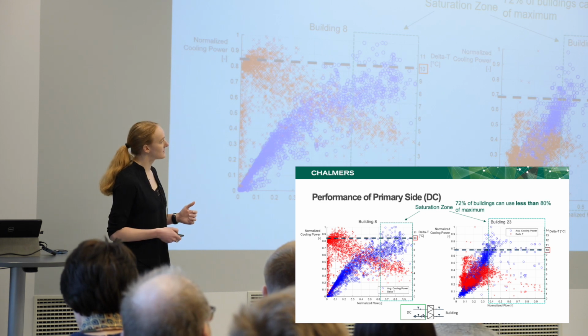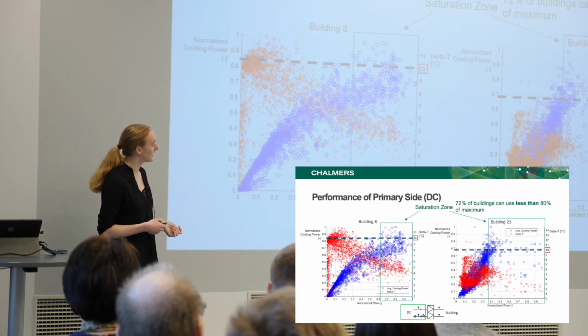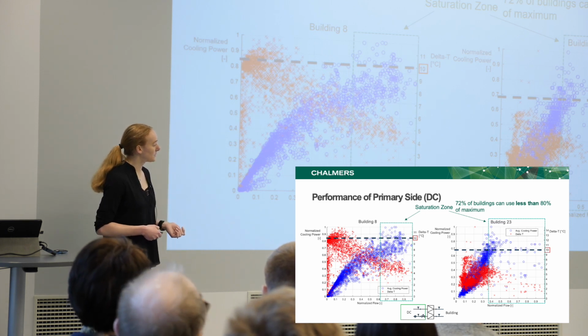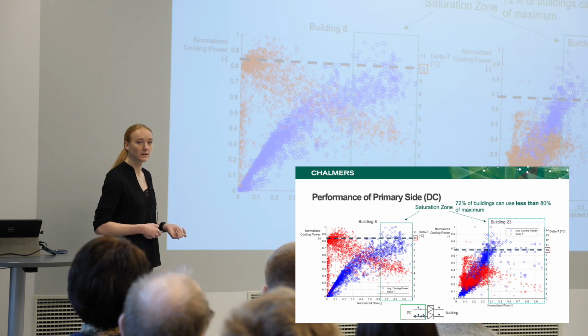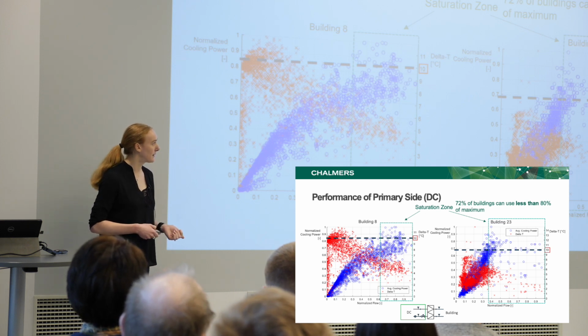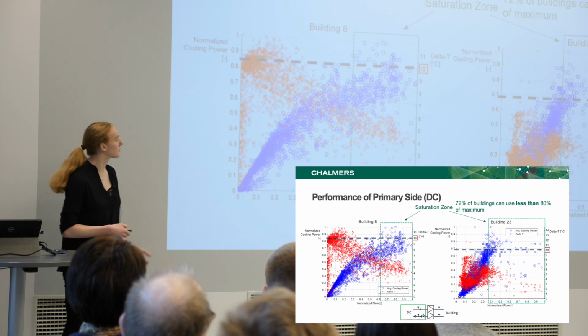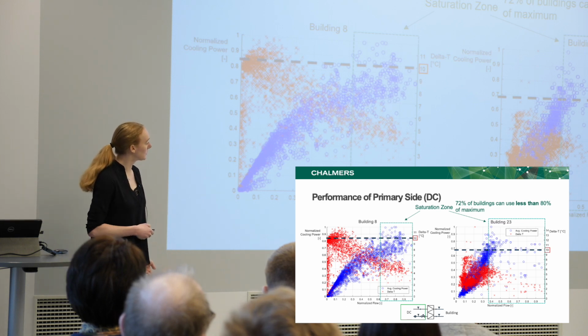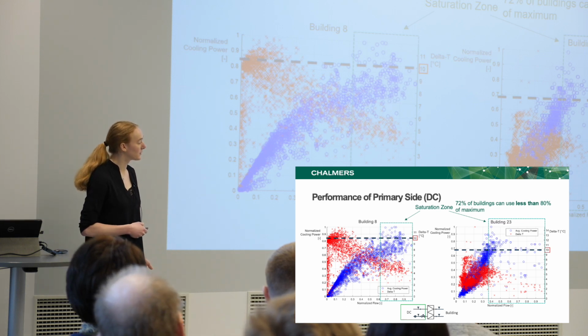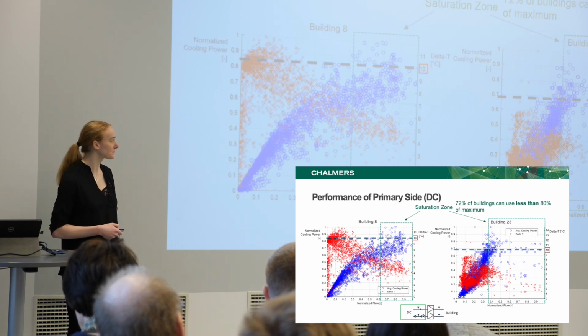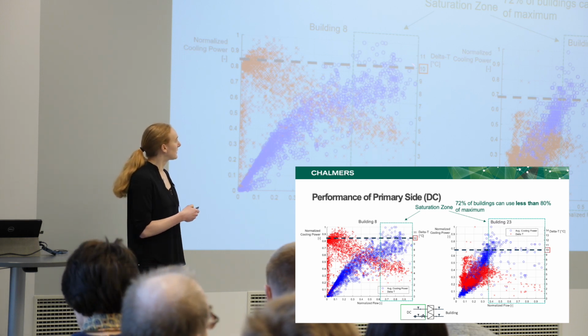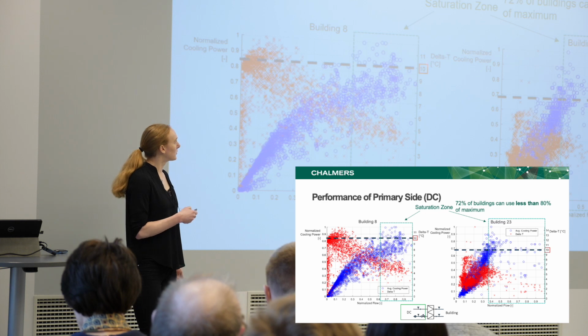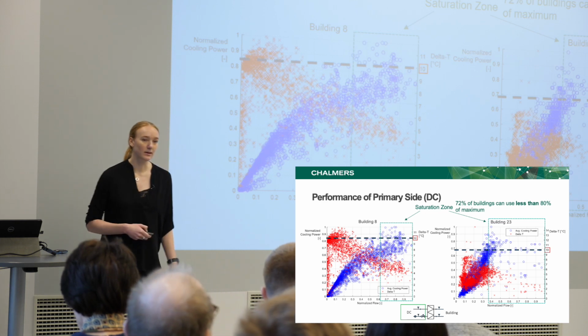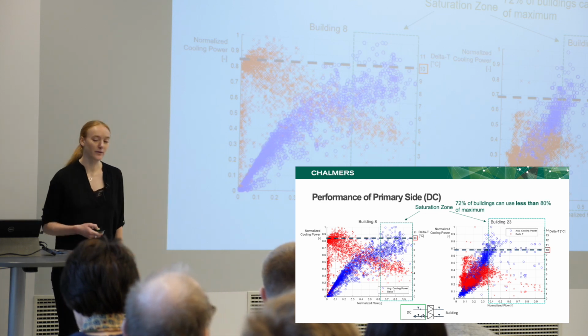But what this means is that it could be good to have some sort of flow restriction here on the primary side, depending on what the building actually needs. So for this one, maybe it's good to limit the flow not to get higher than 70%. Because here the primary side just has to pump more water, and you don't actually get more cooling power out of it.